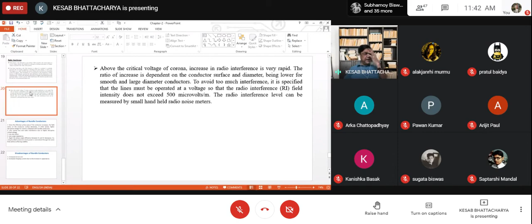Now, in the case of corona, we have seen that if we can increase the diameter of the conductor, then obviously the resulting electric field on the conductor surface will reduce, and there is less chance of formation of corona and less corona loss. Therefore, if we use bundle conductors, then obviously the effective diameter of the conductor will increase and the effect of corona will be less. Now, these are the advantages of bundle conductors.